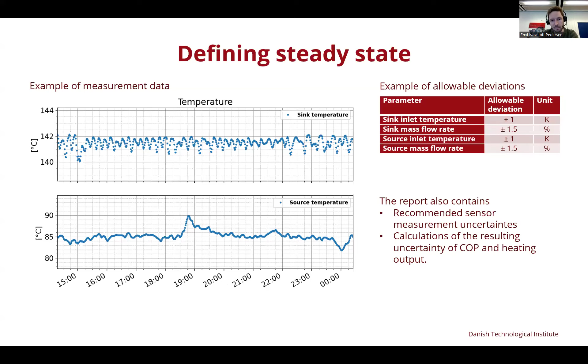Lastly, you might have that your on-site conditions look more like this. So it's really hard to define steady state. And one way to get around this would be to use a simulation-based approach. So you could build a model that you validate for your on-site conditions. So you fit your model to your measurements, and you can replicate these measurements with your model. And then you can use this validated model and run it at design conditions and compare these results with the performance that is promised in your contract with your supplier. Yeah, and then of course, such a simulation model is very valuable and could be used for optimizing the system as well.